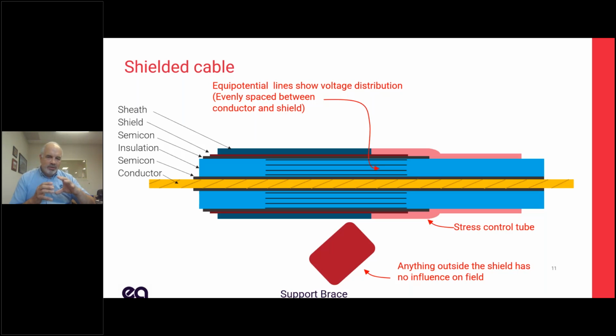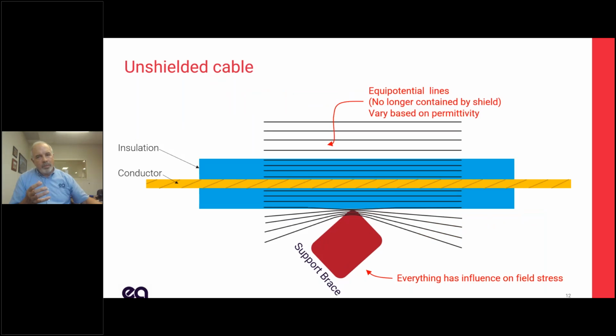So in this picture, I've shown a support brace, an insulating support brace even. It has no effect on the electric distribution in the insulation. And that's really good, because when I'm a cable manufacturer, I can design an electric field strength and an insulation to withstand that strength, and unless that changes, life is good and I don't get any kind of discharge.